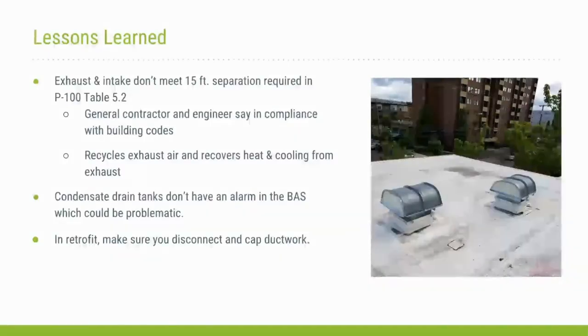So lessons learned. The exhaust and the intake. We've got a P100 requirement that says you've got to have a 15-foot separation between the exhaust and the intake. When I walked up there, they didn't have this on the drawings, incidentally, or we would have pointed it out early on. So there's like 3 or 4 feet separation between those two. It's a Lossnay. It's not a dedicated DOAS system. If it were for the whole building, we'd have a better opportunity to provide that separation. But instead, we've got these 2 little independent controls.